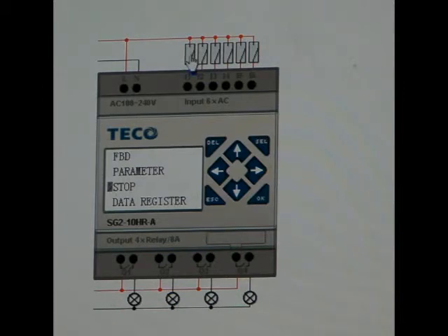For example, if I was to activate an input, which would represent a material switch in this loader, it immediately starts to load and run through the program. This is how the basic system works. Your I/O is up here, your inputs, and your outputs are here. If I wanted to go into the stop, I would generally escape at that point, go back to the I/O screen. You can see the highlighted I/O, so you can always tell what the controller is trying to do from the I/O screen. I have a single input, and the loader is, in this case, loading the material into the hopper. If I turn that off, you will see that it will finish that load, and it won't load anymore, and now it's cleaning the filter in this particular case.